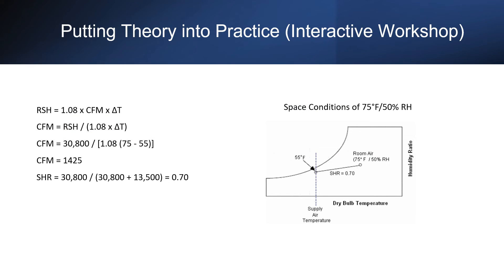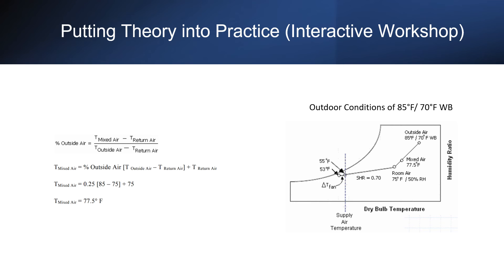Since we know the sensible heat load and delta T, we can calculate the CFM from the following formula, where delta T is the difference between the return air and supply air temperatures. On the psychrometric chart, plot space conditions of 75°F at 50% relative humidity and find the intersection of the sensible heat ratio line with the space temperature and supply air temperature. Then plot outdoor conditions of 85°F dry bulb and 70°F wet bulb.